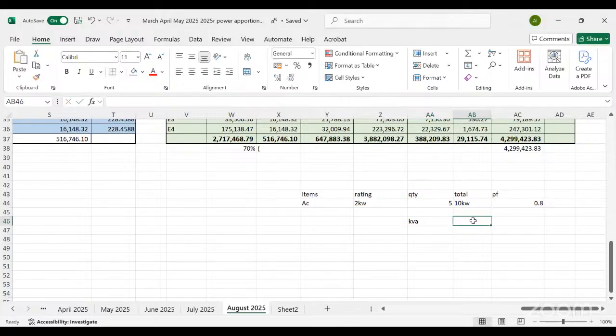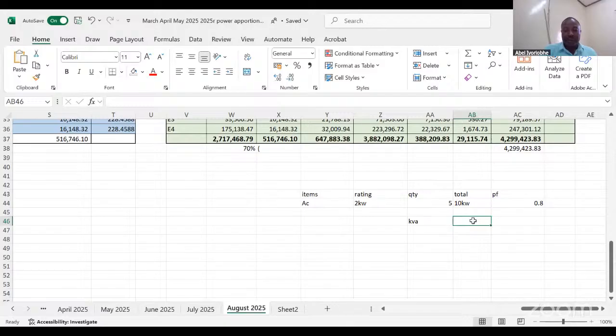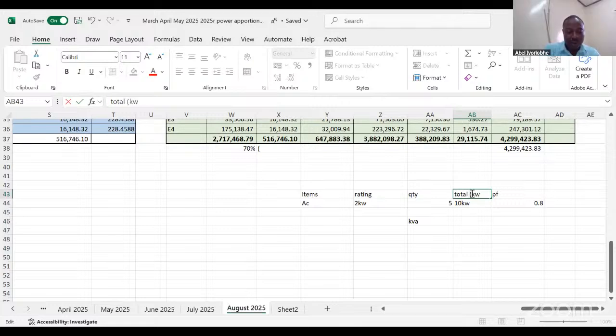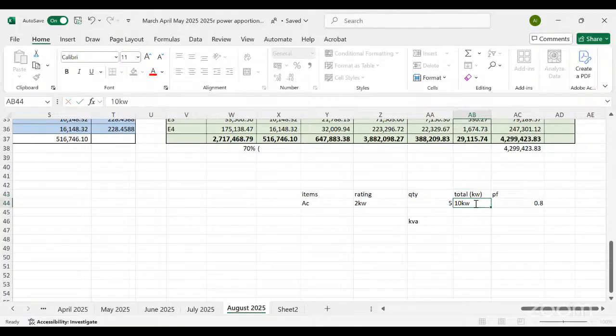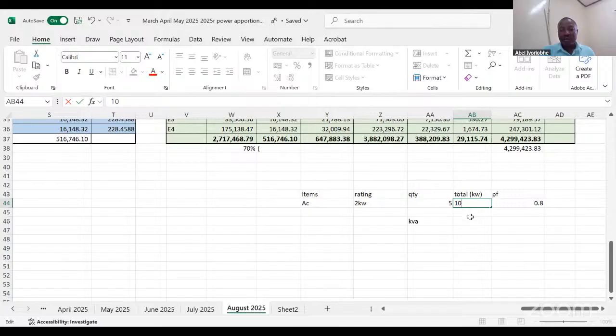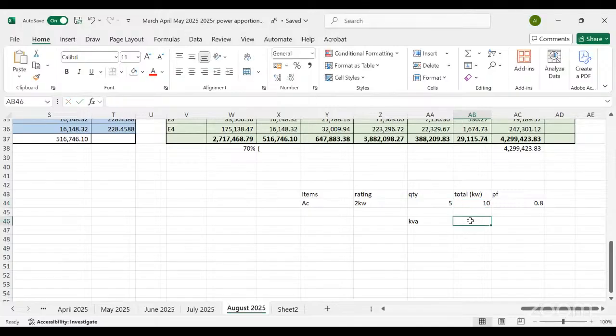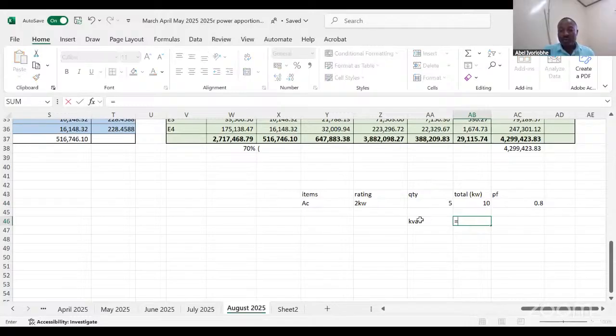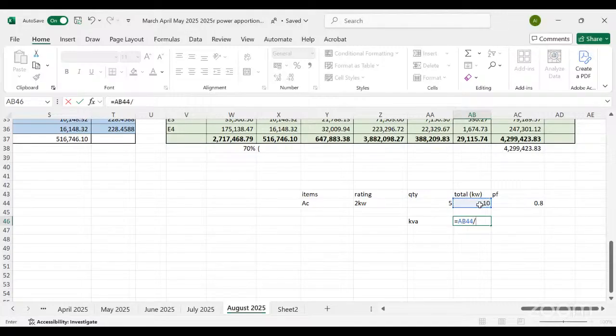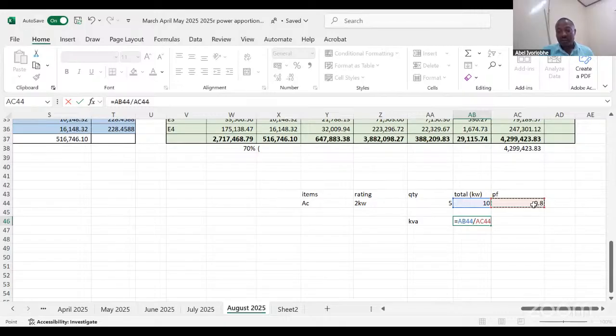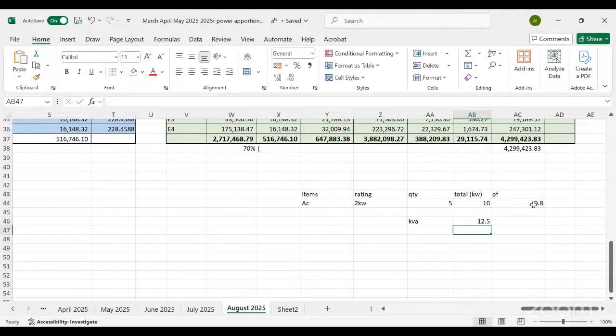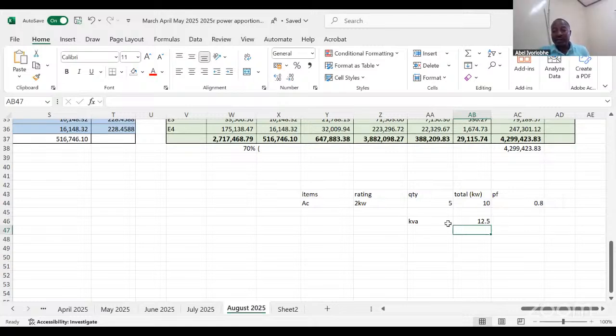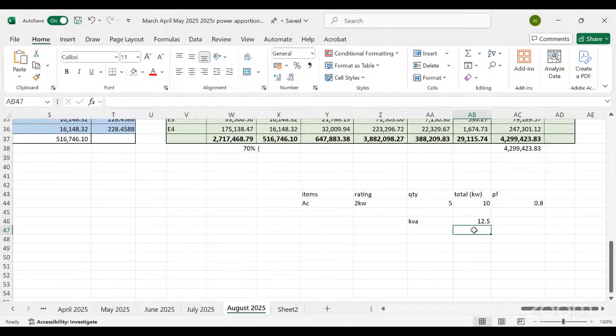Right? So to get this in kVA, let's assume this is in kilowatts now. In kVA, you have 10 kilowatts, right? Your generator size for this load will be equal to the 10 kilowatts divided by your power factor. Power factor 0.8. Please write it down. So you have 12.5 kVA.